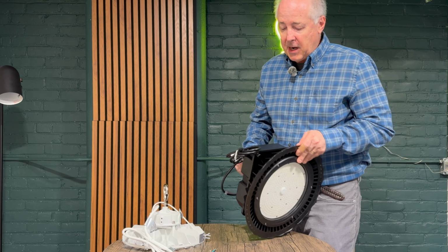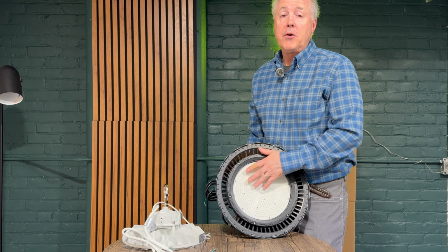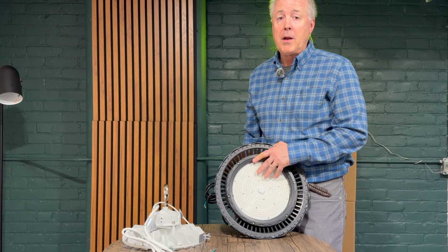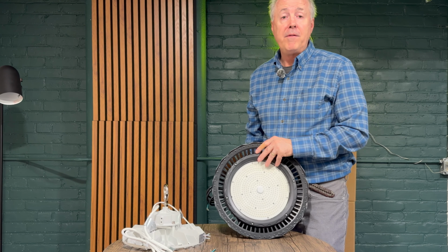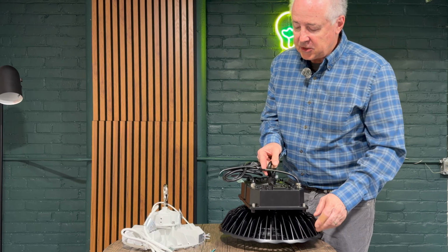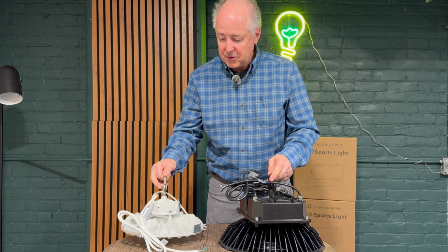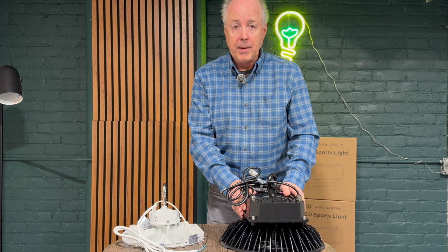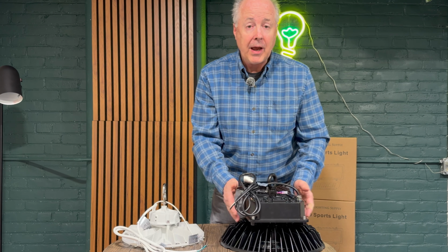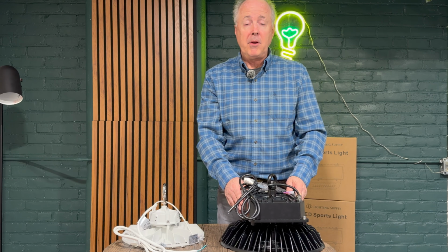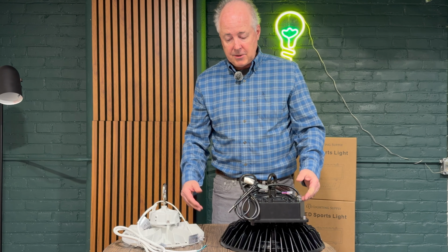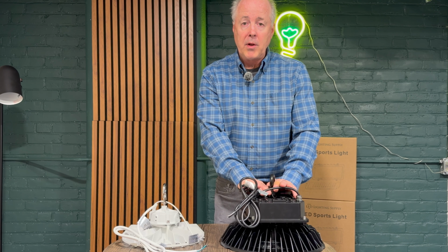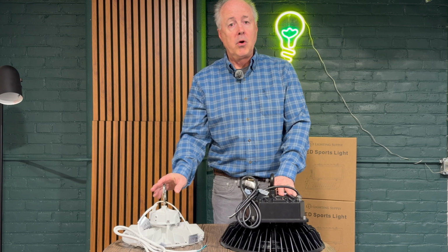You can also put a 90, 60, even a 30 degree optic on this. This one replaces a 1000 watt. We have some that go even higher, up to a 1500 watt metal halide. But again, it's just the extreme. This fixture is probably 7 or 8 pounds. This fixture is 20 pounds. A lot more to it. The driver is inside the junction box, easily replaceable. It's just a monster of a fixture. If you have industrial applications, you definitely want to go this route versus a more commercial light.